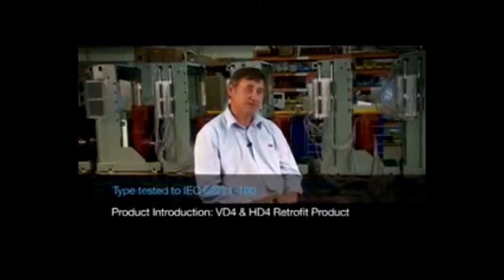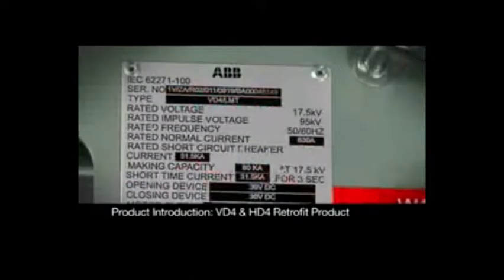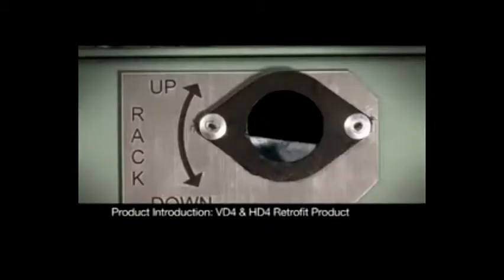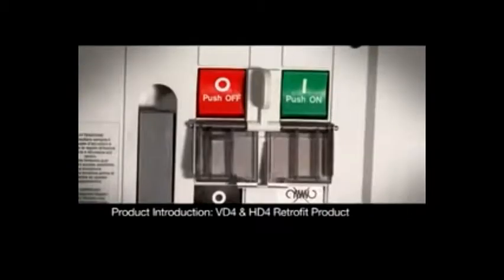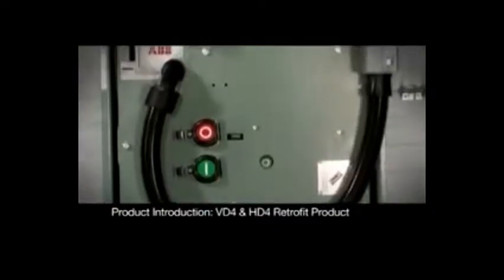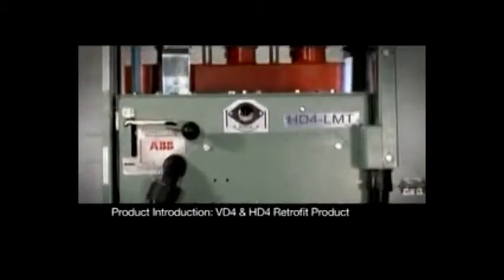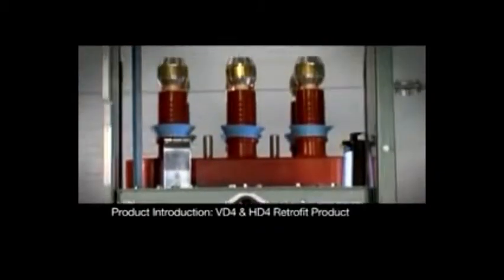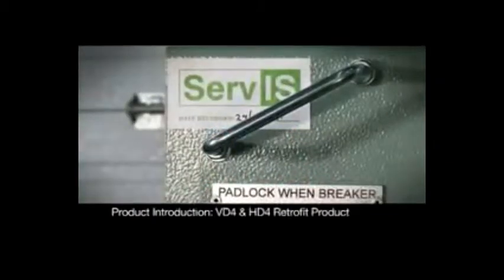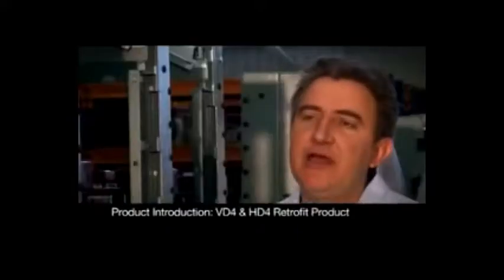We do partial discharge testing as well during the type testing process, which then ensures that dielectrically we know our product can handle harsh environments. With retrofitting, you minimize downtime. There's minimal changes that you need to do to the panel to fit new technology. The cost of retrofit is typically 50 to 60% the cost of replacing the switchgear. It will be less disruptive to their services because they take the unit that's currently in there, they take it out, they install the new unit, and they can immediately carry on with their production.